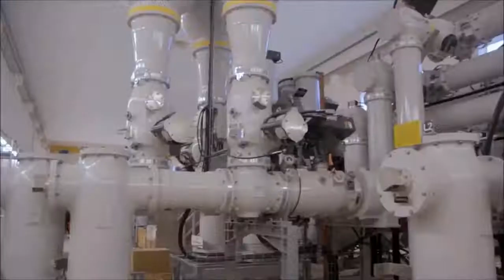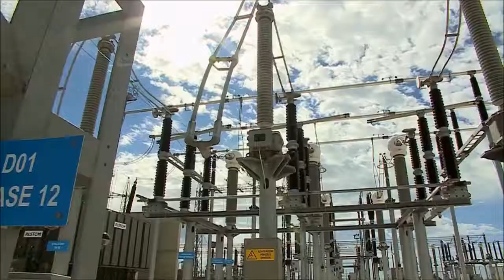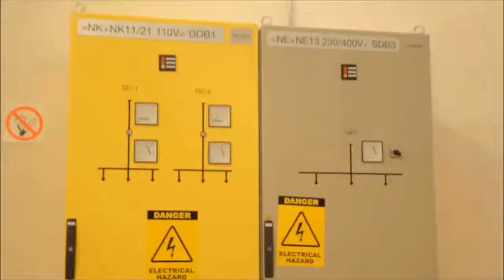Over 98 kilometers of submarine cable, almost 20 kilometers of land cables, a bidirectional flow capacity of 200 megawatts of electricity at 230 kilovolts. This is the Malta-Italy Interconnector, the longest high-voltage alternating current interconnector of its capacity in the world.